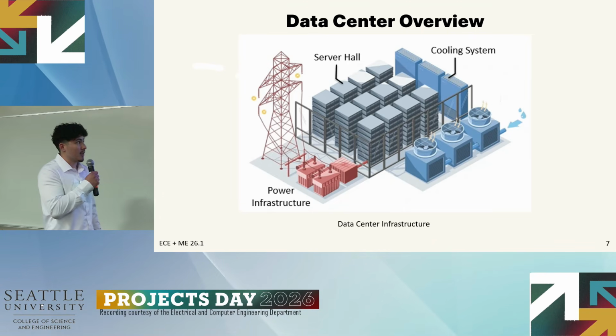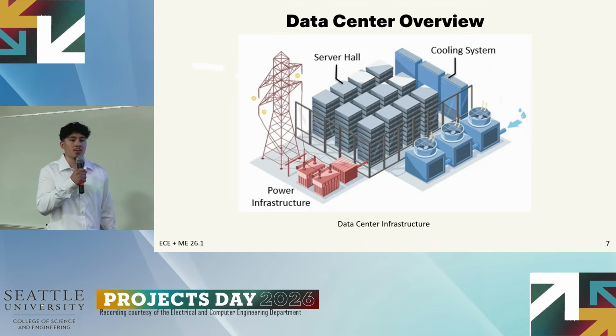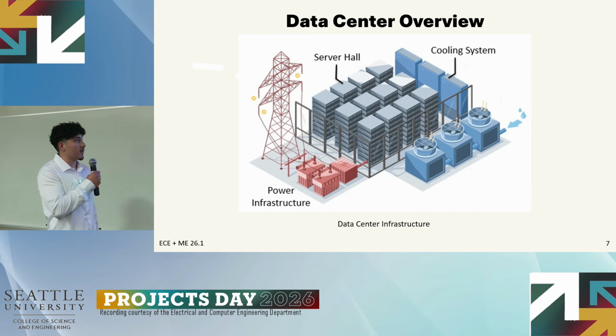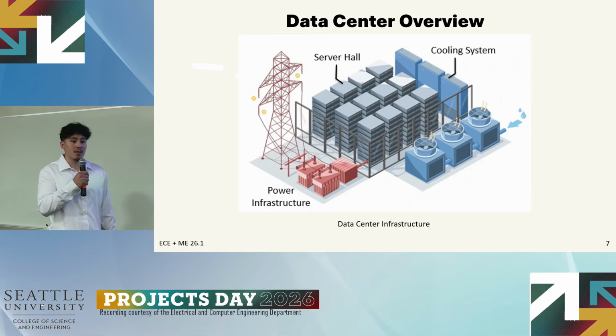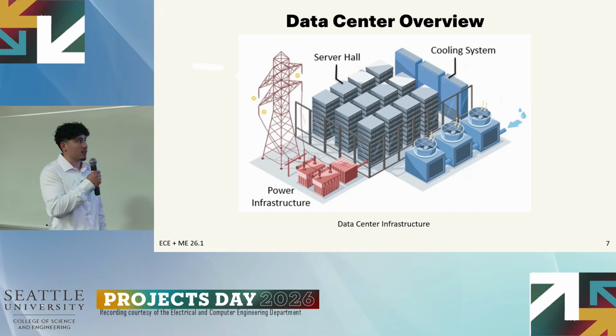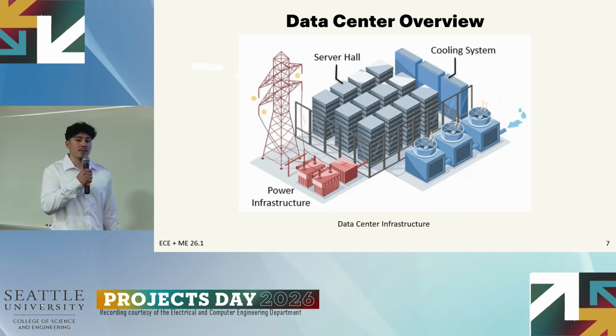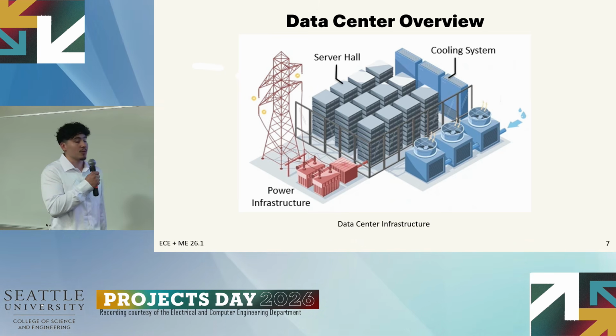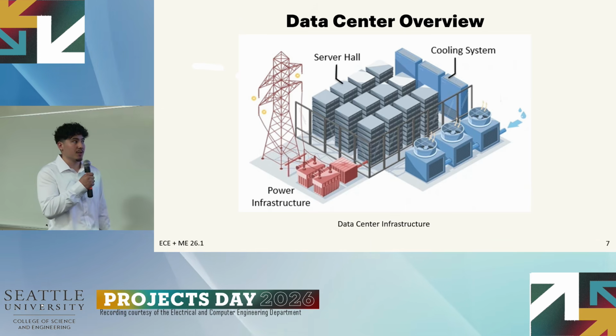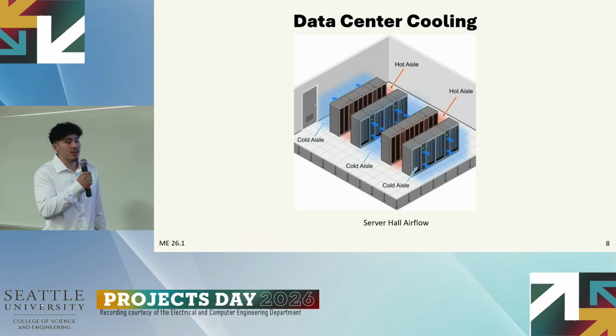So let's go over the general layout of a data center. The infrastructure is built around the computing of servers. These servers are stored on racks and aligned in rows, held in large rooms called server halls. Power is brought in from utility grids externally, then conditioned and brought into the facilities where it is distributed to the server halls and the cooling infrastructure, which keeps those servers from overheating so they can operate efficiently. So let's go further into the cooling.